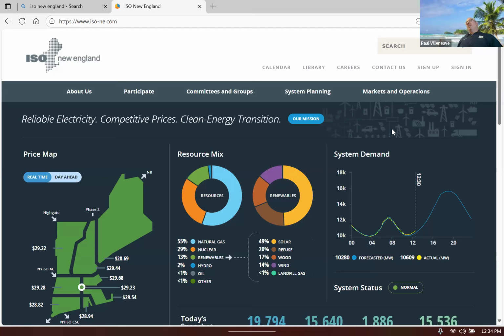So really, the load has to be projected to be there - doesn't necessarily have to actually be there, just projected - because some of these plants take 3-5 years to build. That's from the day somebody says let's build a plant: you have to get permitting, make sure the utility doesn't have issues, study the system. It's a really long process. Once you're ready to build, it might take less than a year, but often 3-4 years, so they're projecting this needs to be done.